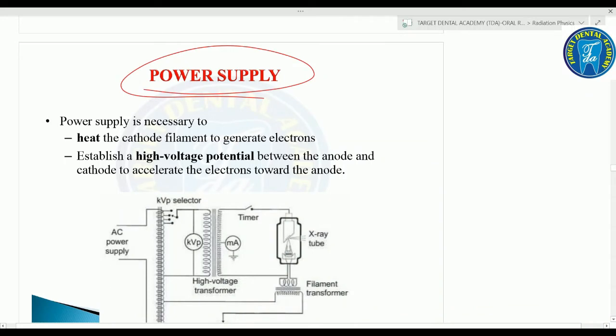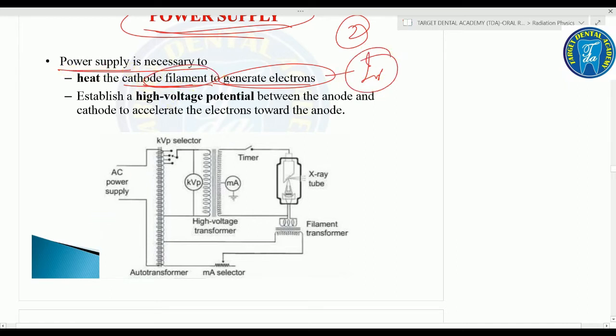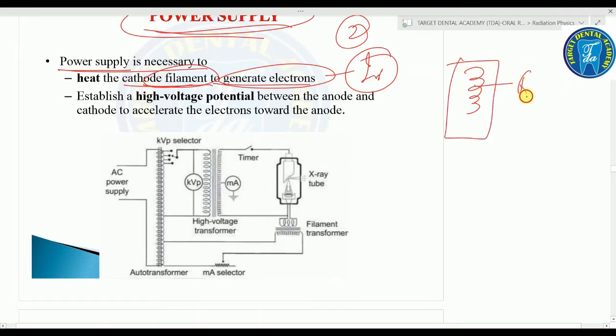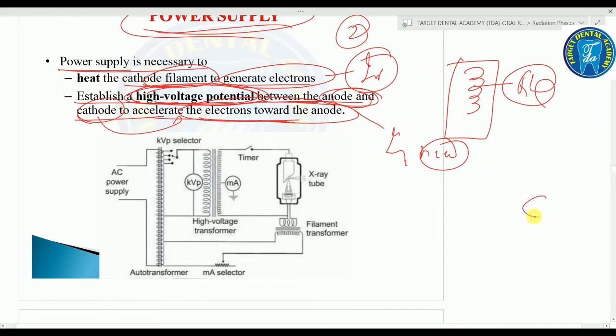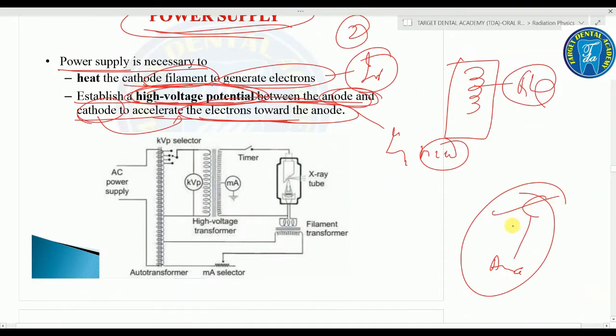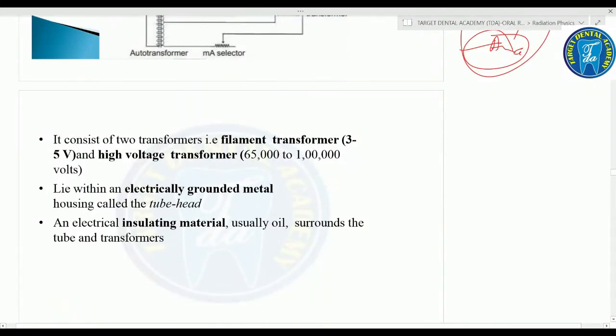Coming on to the power supply: it is necessary to heat the cathode filament to generate electrons and to establish a high voltage potential between the anode and cathode to accelerate electrons toward the anode. A high voltage potential (HVP) is generated between cathode and anode to move electrons from cathode to anode. The power supply consists of two transformers: a filament transformer and a high voltage transformer.